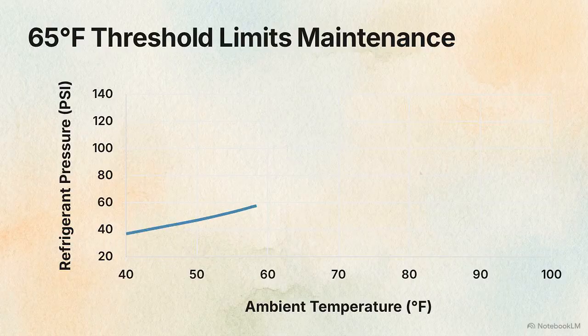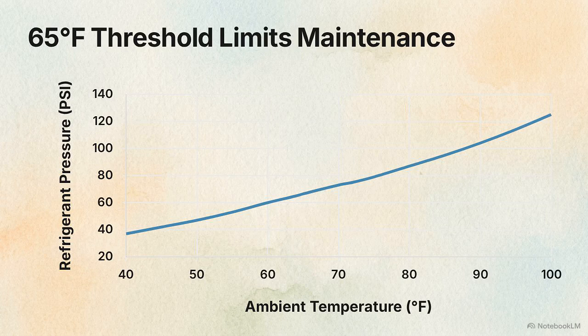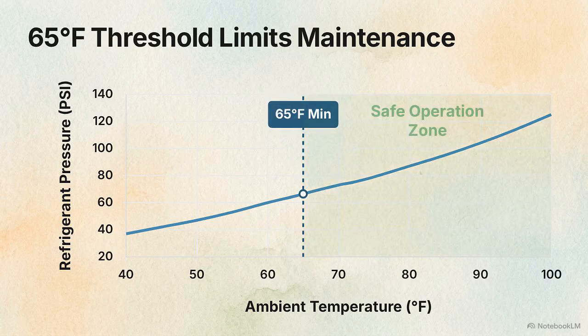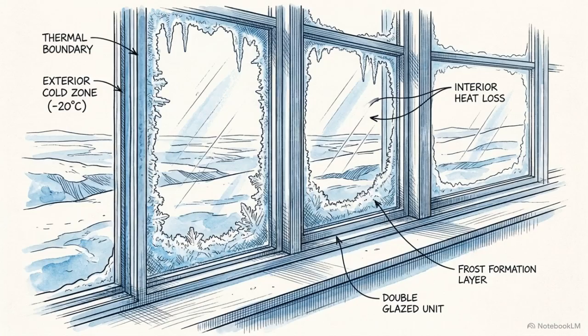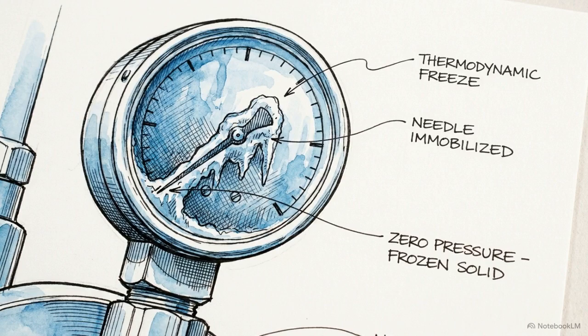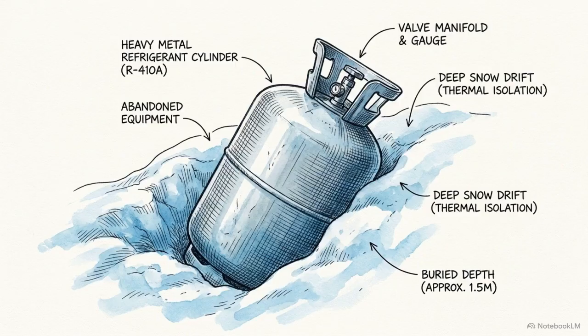This chart shows the direct mathematical relationship between the ambient outside temperature and the internal pressure of your refrigerant system. To get an accurate gauge reading and correctly charge the system, the outside air must be at least 65 degrees. This 65-degree threshold establishes the safe operation zone. Below that point, the system simply cannot build sufficient internal pressure to operate normally. This limits winter diagnostics. If you suspect an issue in February, a technician cannot accurately test. They cannot tune the system or charge your refrigerant levels.